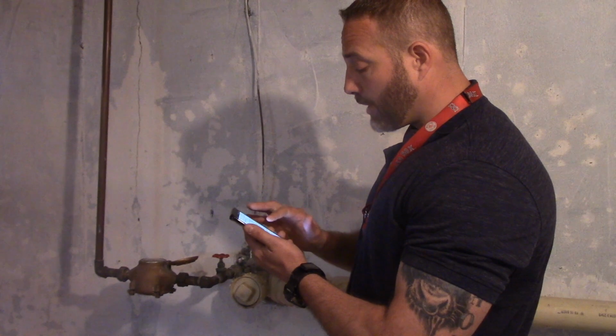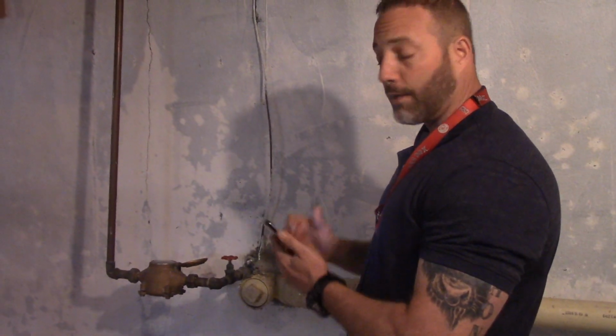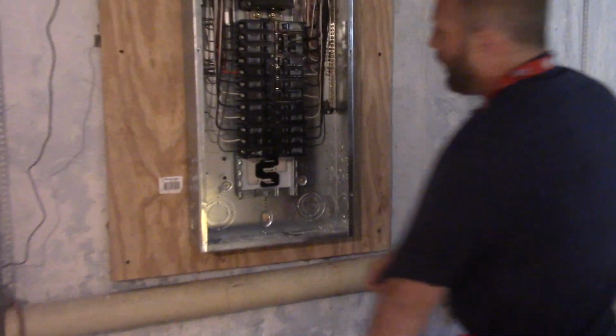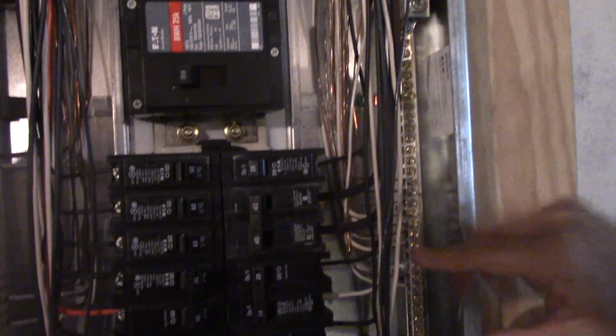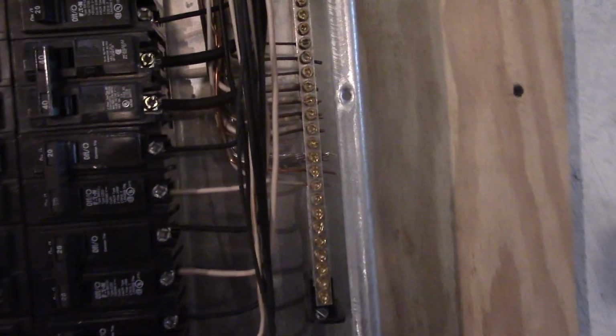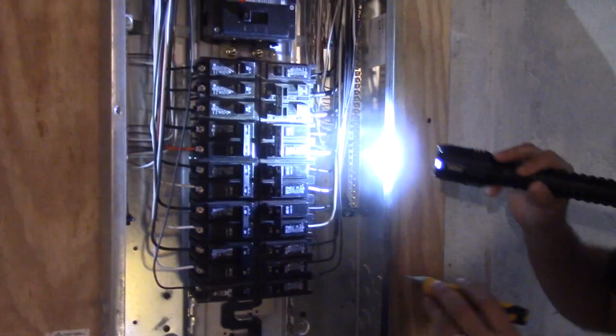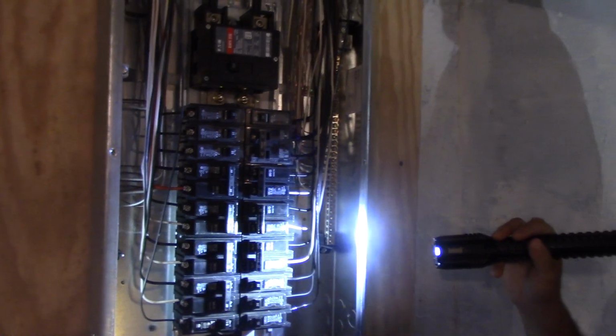All right. And then the last item we have here, aluminum branch wiring. So let's take a look back at the electrical panel here. And we're going to look for aluminum branch wiring. Now, you're allowed to have stranded aluminum, which you have right here. And that's completely acceptable. What we don't want is a single strand aluminum. Because this is all Romex and there is no cloth wiring, I didn't see any aluminum wiring. So today we do not have any single strand aluminum wiring.